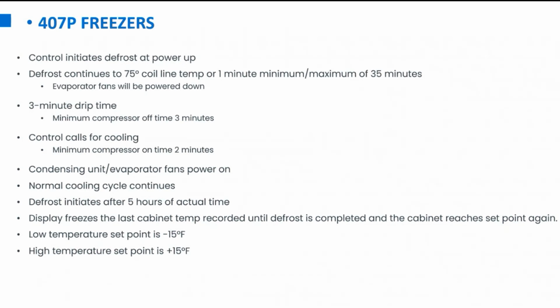This one can be set all the way down to -15. I don't really see a scenario where you probably want to set it that low, just because you're going to have some pretty increased run times there. So normally, if you're giving us a call, we're normally going to tell you to set that thing around 0 degrees, maybe down to -2 or so. And that's typically where we'd want to see those set.